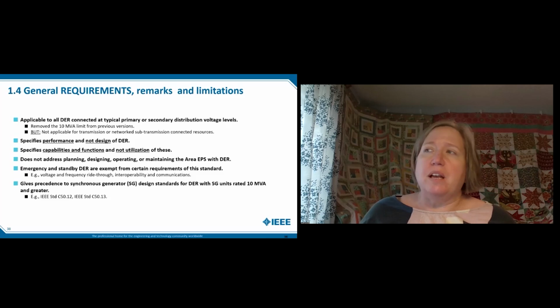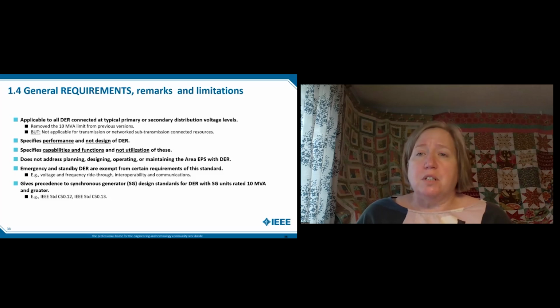It does not address the planning, designing, operating, or maintaining the area EPS that has the DER. Emergency and standby DER are exempt from certain requirements, such as ride-through, the interoperability, and the communications. And then for synchronous generators greater than 10 MVA, we use things such as the IEEE C50 standards that are for synchronous machines. So we're giving precedence to the existing standards on synchronous machines.